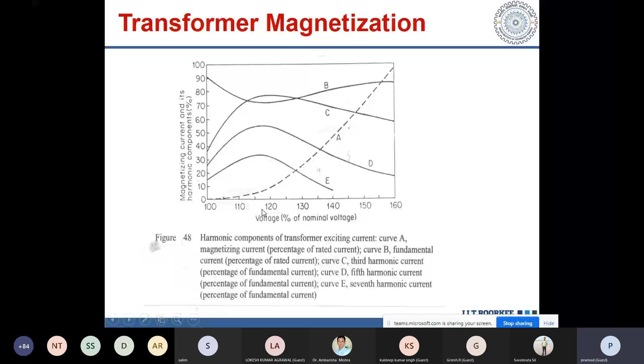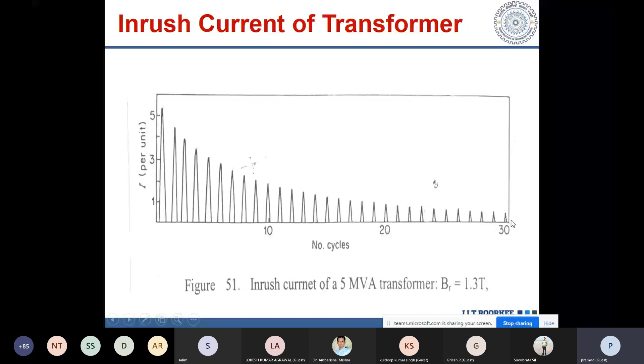Again, whenever you switch on a transformer, there will be inrush current. We know that the initial current may be 5 to 7 times the rated current. Although it keeps on decreasing with each cycle, it may be present for a good number of cycles. This is also a power quality problem.